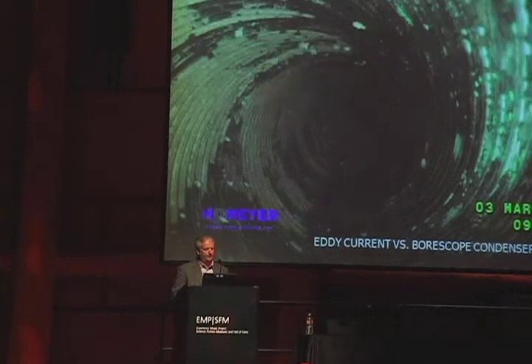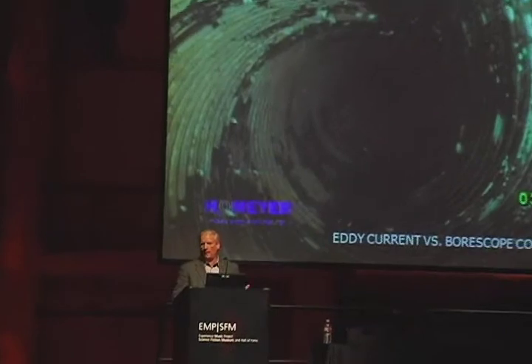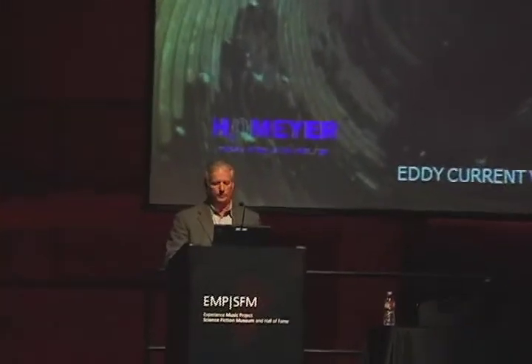So it's always a good idea to try to do both borescoping as well as eddy currents in between times to find out what's going on. The nice thing about borescopes is that you can see what's going to happen to you in a couple years. Eddy currents obviously tell you whether or not you're actually seeing metal loss in the tubes.